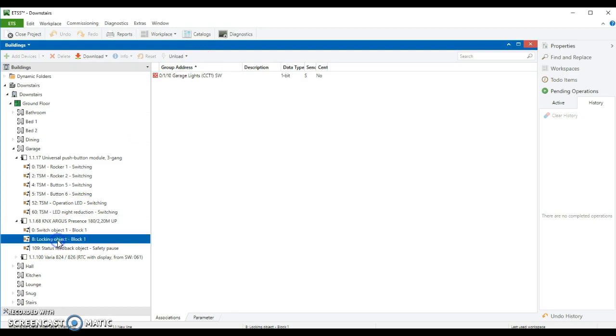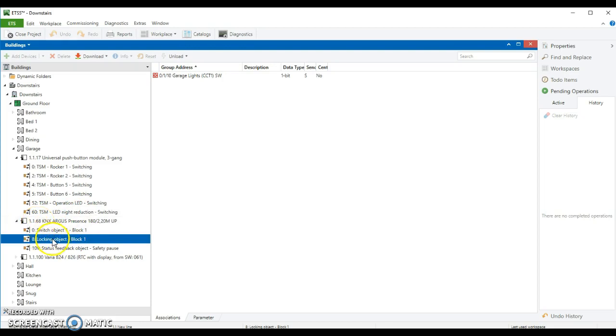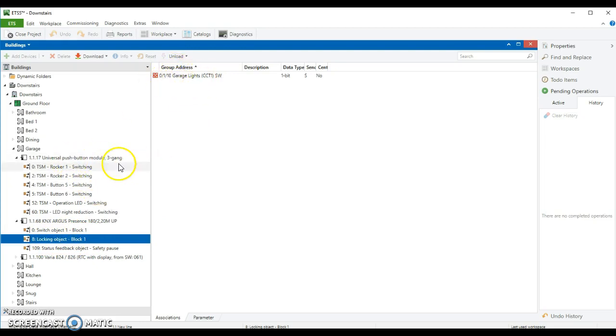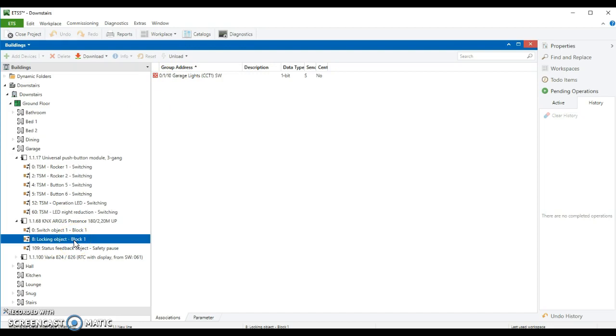But also it's listening. So looking at the locking object or the blocking object, the nomenclature is slightly different depending on the manufacturer. This locking object channel is listening to that switch. So when this push button switch is switched on, this listens to that and it will initiate locking. And therefore no timer will run until you actually turn this back off again.